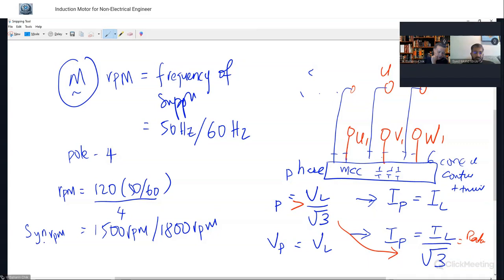For an AC induction motor, it will run less than this speed. For example, it will run 1497 RPM or maybe 1797 RPM. Because for an AC induction motor, it cannot run at the synchronous speed since you cannot align the magnet together with the stator. So the rotor will turn a little bit slower. Otherwise, the rotor cannot rotate if they are in sync together.